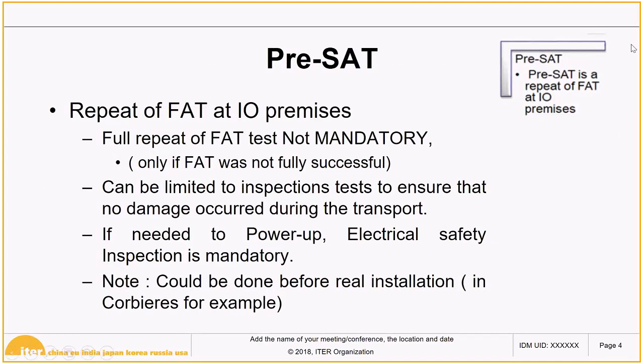On the scheme, we have always put pre-SAT, written as a repeat of FAT at IO premises. A lot of people understood that as an obligatory step, but it is not at all mandatory. What we need to do is only repeat the part of the test which was not successful. If the FAT is completely successful, this pre-SAT will be limited to inspections and tests to ensure no damage occurred during transport. If we need to do some power-up, there is a need for electrical safety inspection, which is mandatory, and if needed, this step could be done not on site, but before, for example at Corbière, or before the real installation. So if we have some troubles, we can organize this.